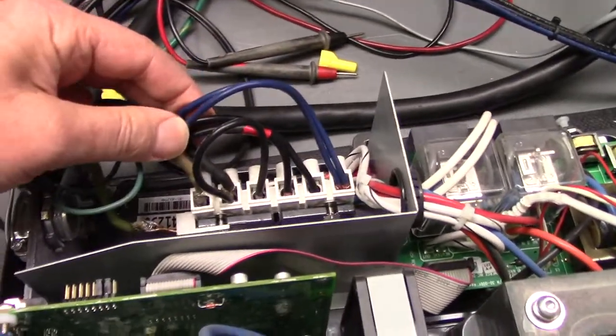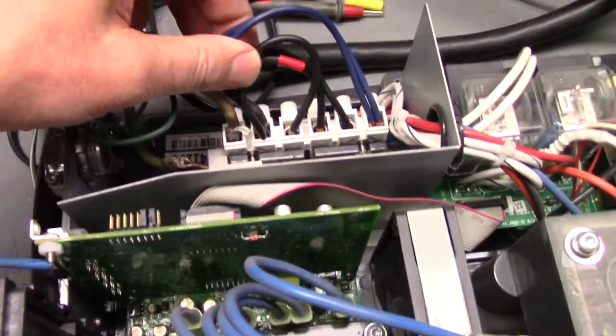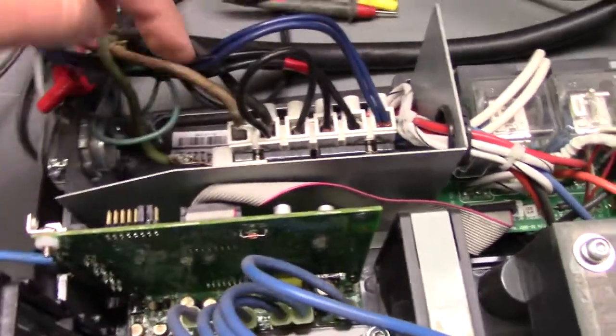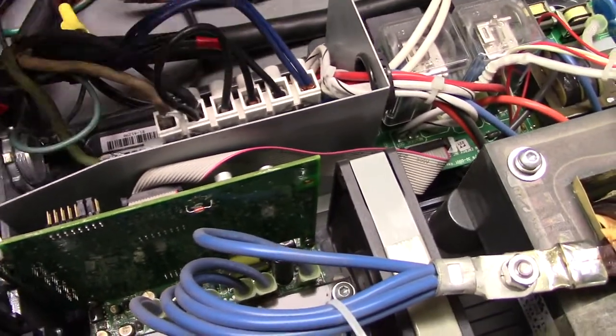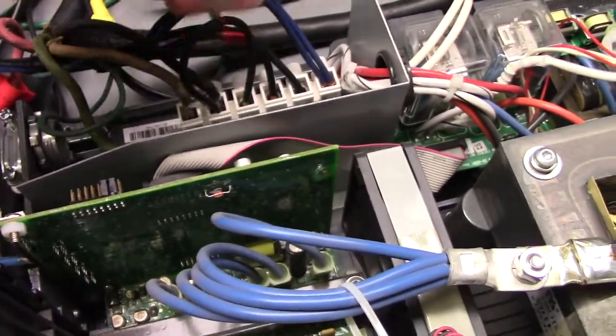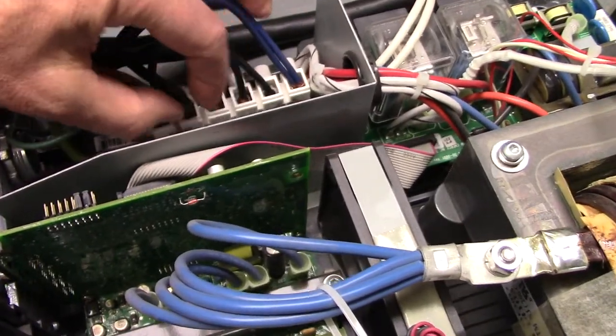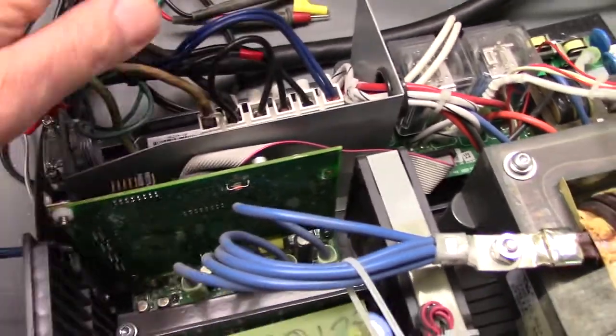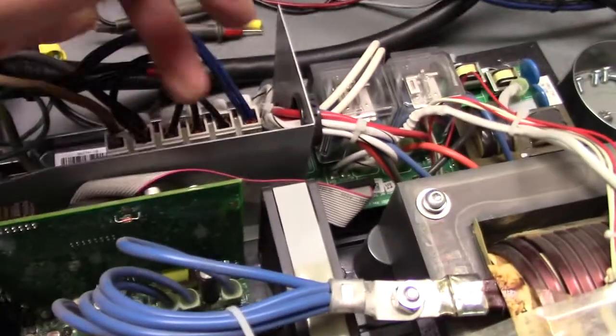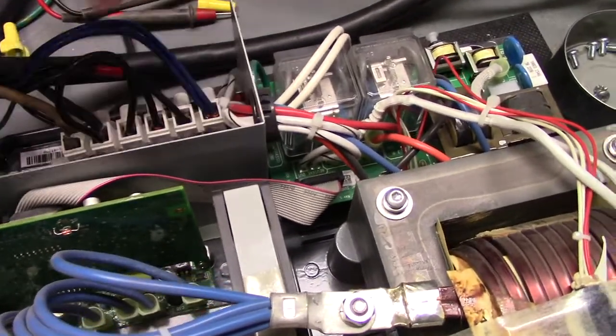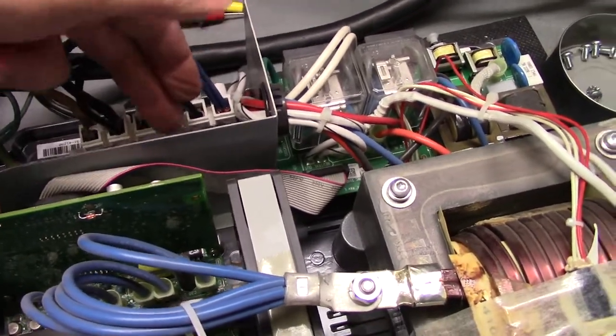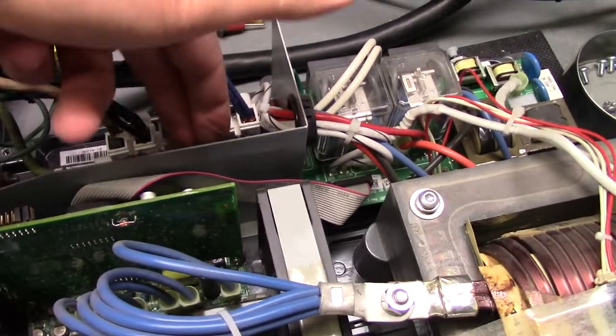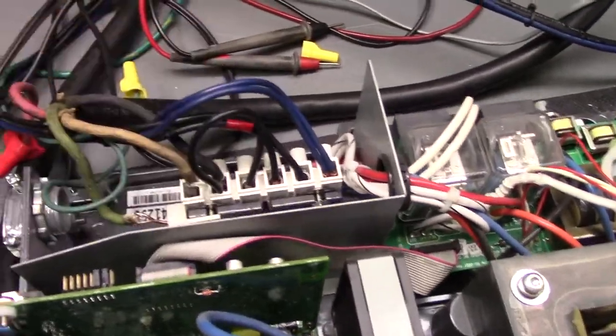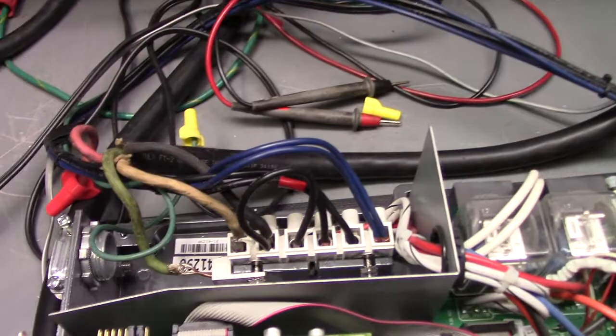You can also feed 240 volts to this input. You'd have your neutral, your L1, L2, but you would actually have 240 volts here. You wouldn't have this jumper. You would have 240 volts across that point, and that's perfectly acceptable in these, and it will simply come out 240 on the other end, with neutral. So then you have 120 to neutral, 120 to neutral, 240 between two hots, and that's an acceptable way to wire these units as well.